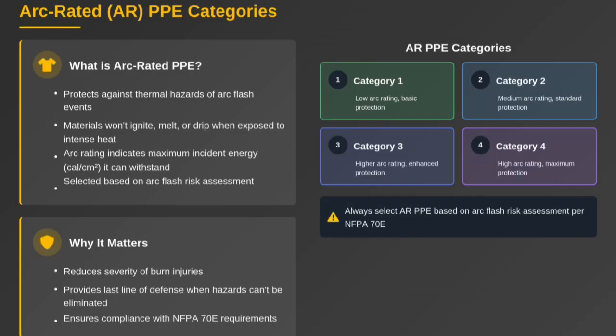Arc-rated, or AR PPE, protects workers from the thermal effects of an arc flash. There are 4 categories. Category 1 offers basic protection. Category 2 provides standard protection. Category 3 increases the protection level, and Category 4 gives maximum defense against extreme heat and energy. Always select PPE based on your arc flash risk assessment. AR clothing doesn't ignite, melt, or drip, and that can mean the difference between life and death.